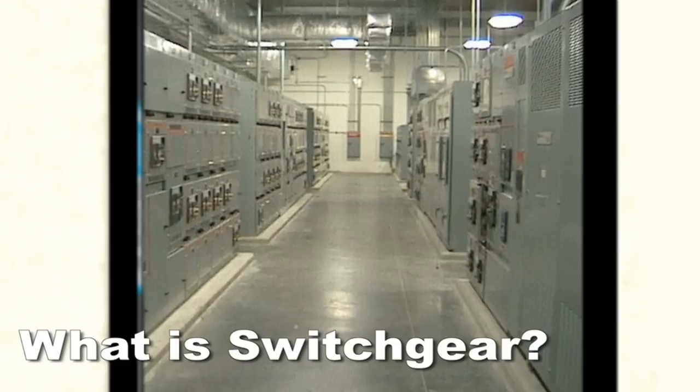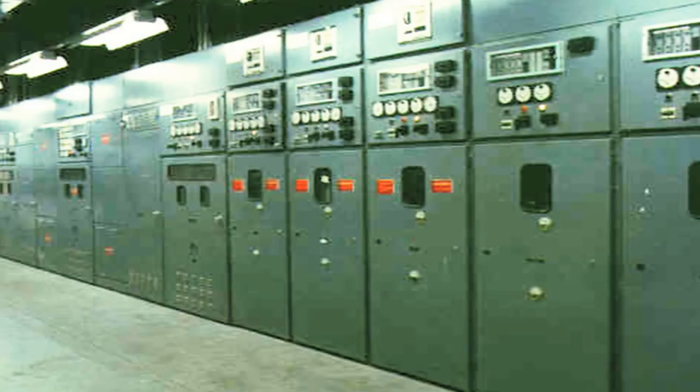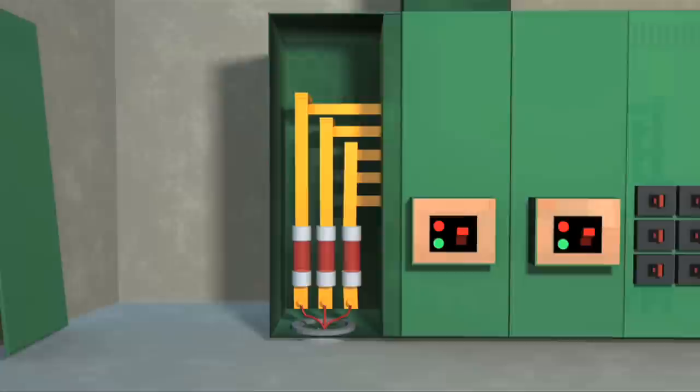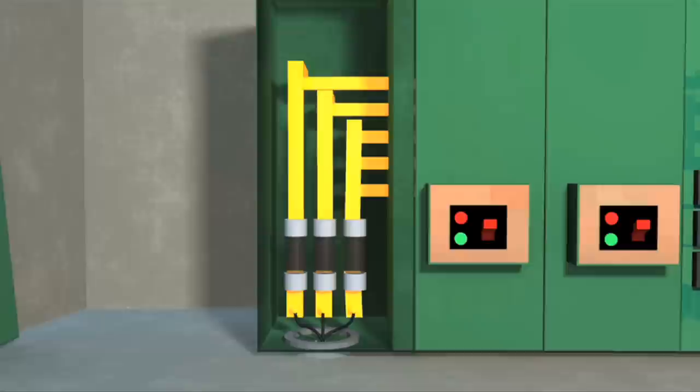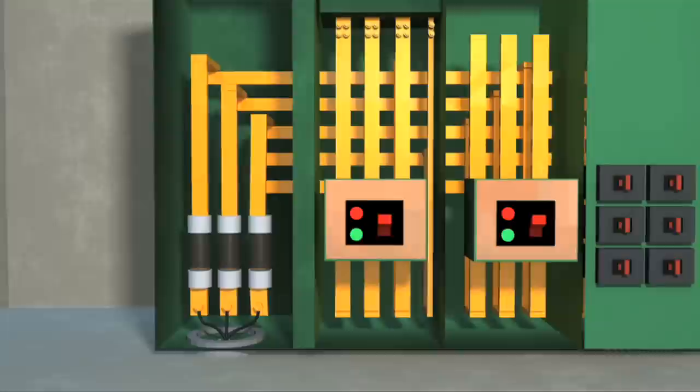What is switchgear? It's the beginning of the electrical distribution system inside the facility located in an electrical room. It is made up of several sections containing switches and or breakers. The first section receives the incoming power from the oil transformer. The wires are connected to a main breaker, or in this example, they are attached to fuses. The fuses are connected to bus bar. Bus bar is either made up of copper or aluminum.